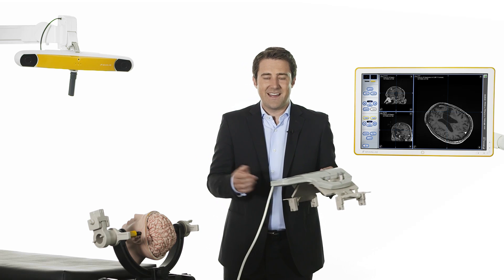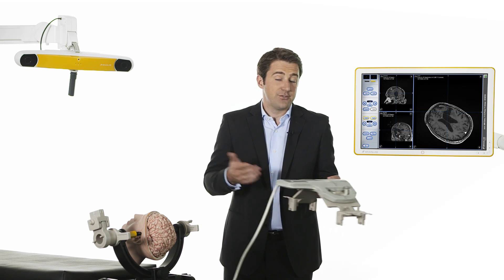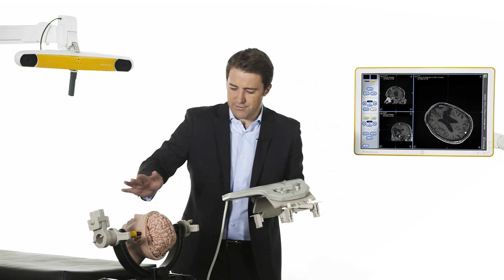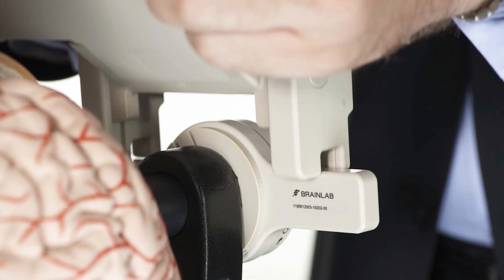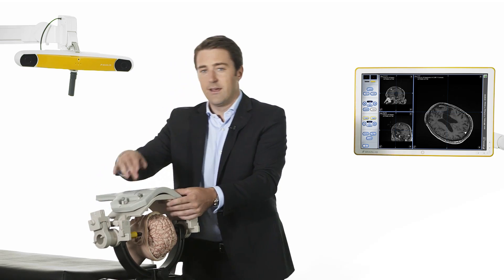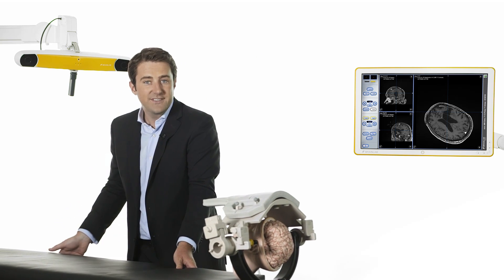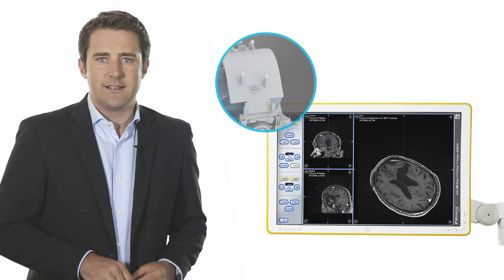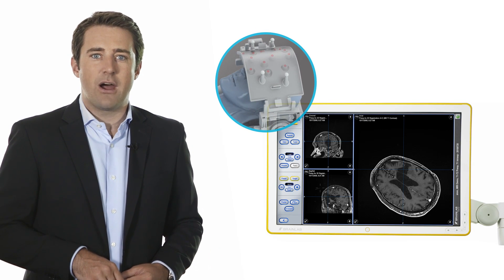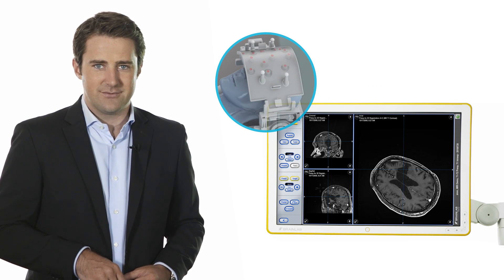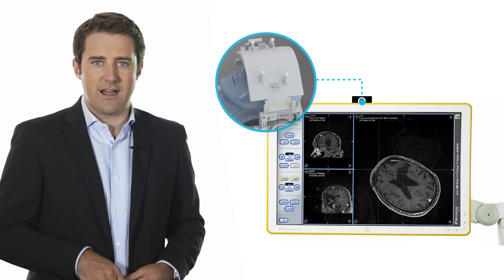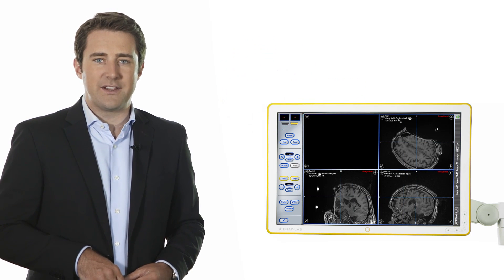To update anatomical data during the procedure in order to assess brain shift or for resection control, the surgical field is draped and the matrix is mounted to the headholder. Shuttle systems ensure smooth patient transport from the OR table to the scanner. Images are acquired with the MR markers included in the scanner's field of view. Immediately after the scan, data is automatically transferred to either a ceiling mounted or mobile navigation system.